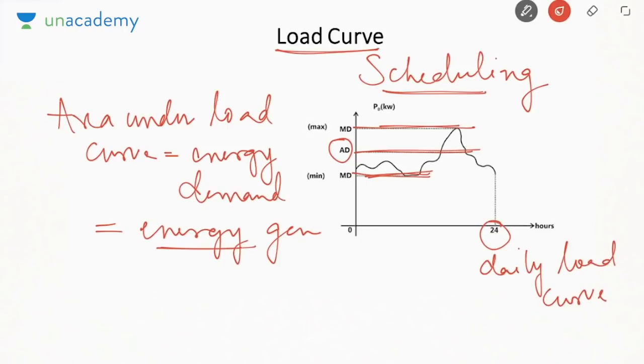So how is a daily load curve useful? It is for the control of power system. That means what power must be generated during what time of the day. Which generator should be operating during the daytime, which should be operating during the night time. That way we can control the generation to supply the daily load curve.